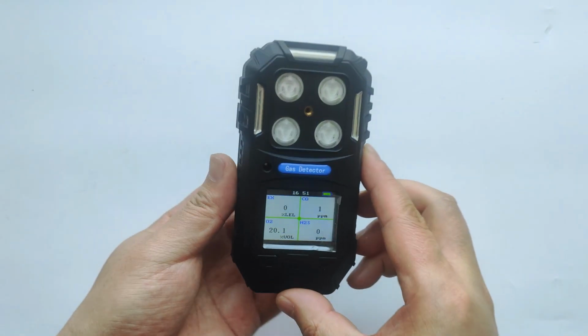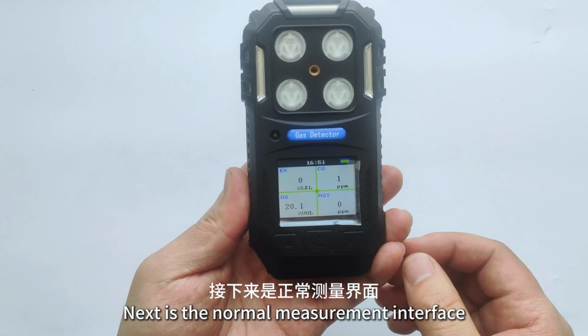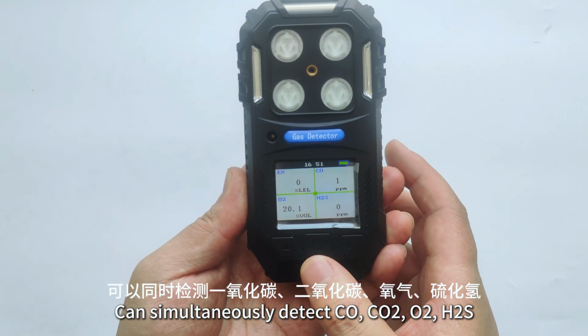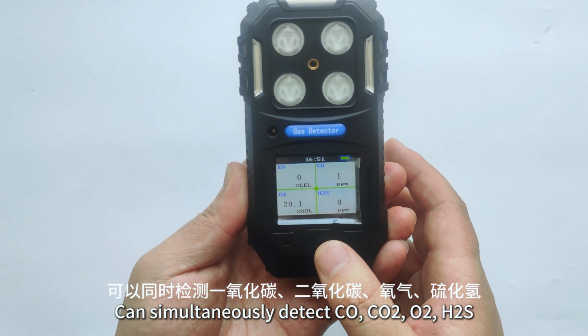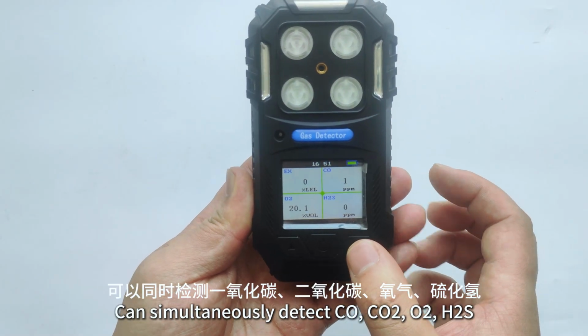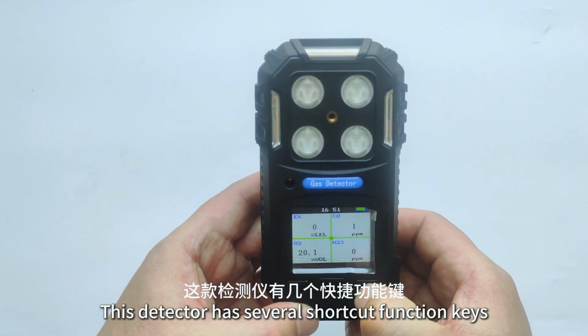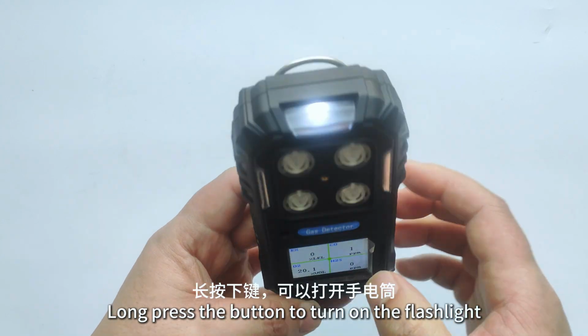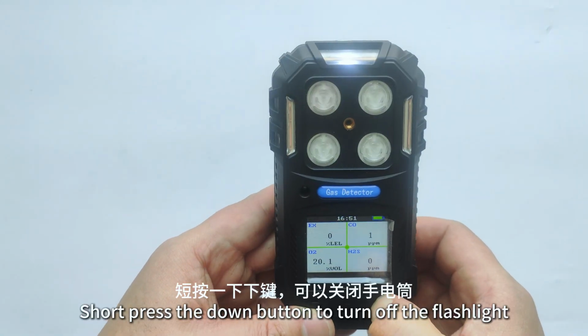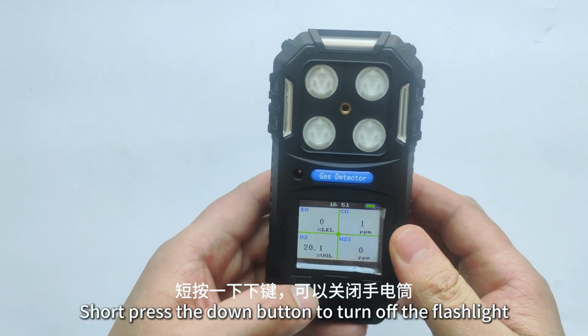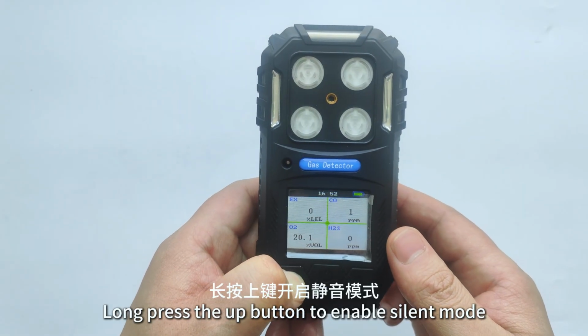After booting, next is the normal measurement interface. Can simultaneously detect carbon monoxide, carbon dioxide, oxygen, hydrogen sulfide. This detector has several shortcut function keys. Long press the button to turn on the flashlight. Short press the down button to turn off the flashlight. Long press the up button to enable silent mode.